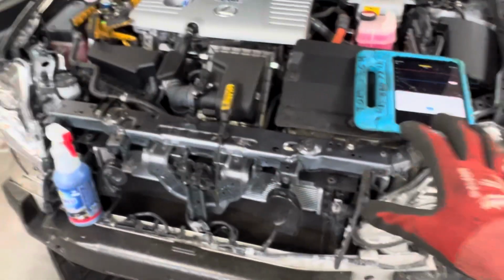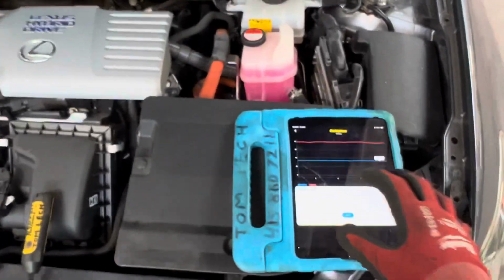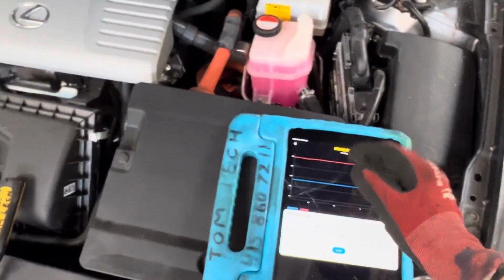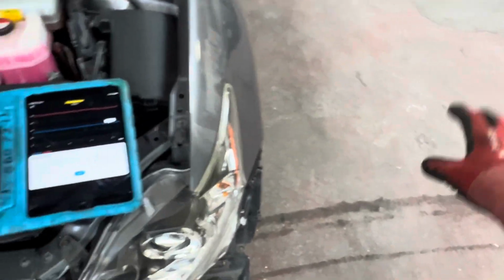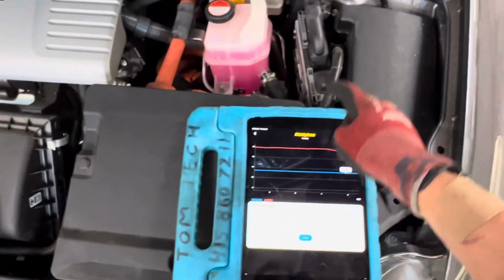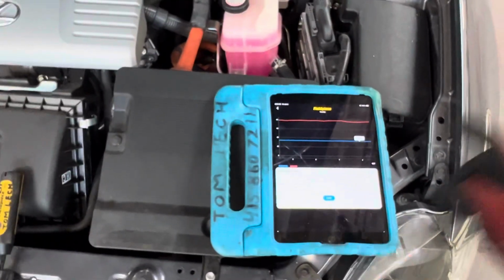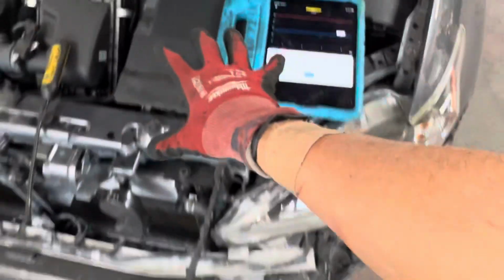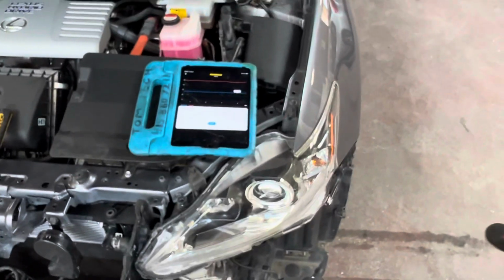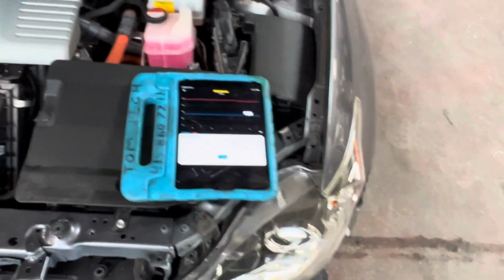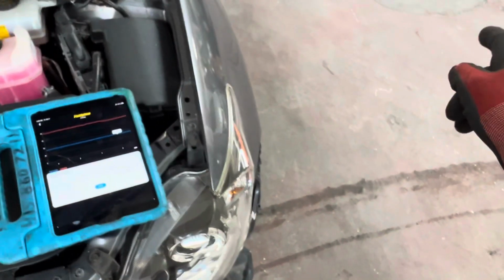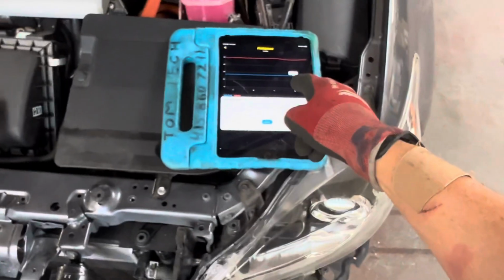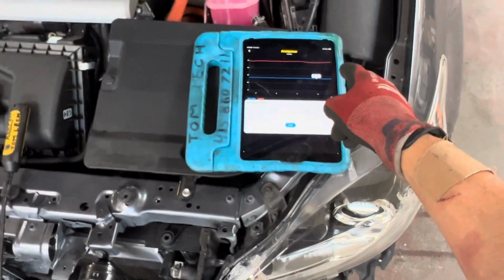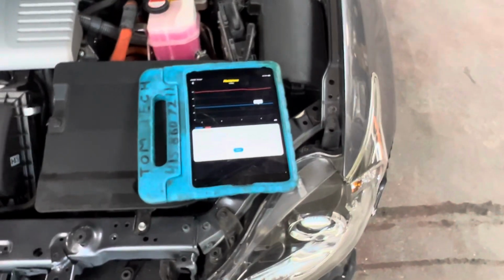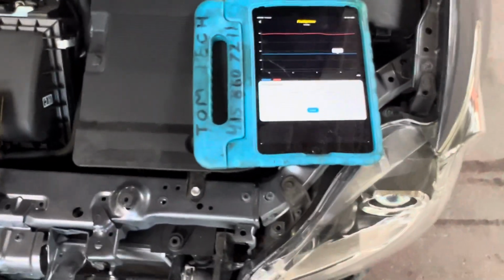You really got to get, if you've watched enough of my videos and you've seen them cycle up and down, you've seen a normal vehicle. I could have another vehicle, like an old BMW right here, and the high side pressure would go up to 270 PSI right now. And it'd sit right next to this car, inside this garage, no sun on it, no heat load, and it would go to 270 PSI. This one only does 80 PSI, 79 PSI. So how can you get a rule of thumb or some sort of average?